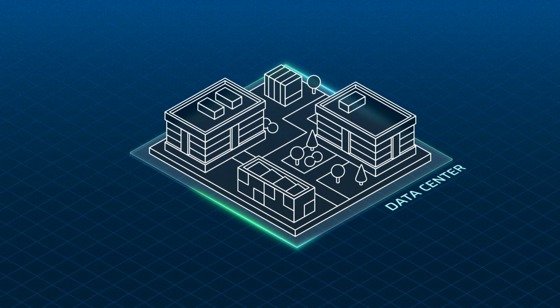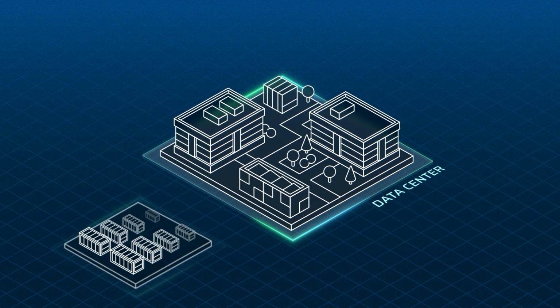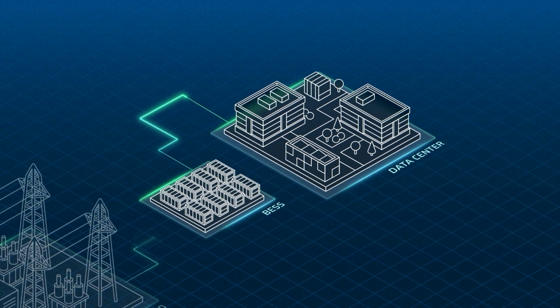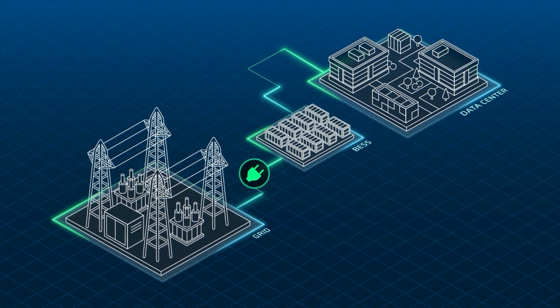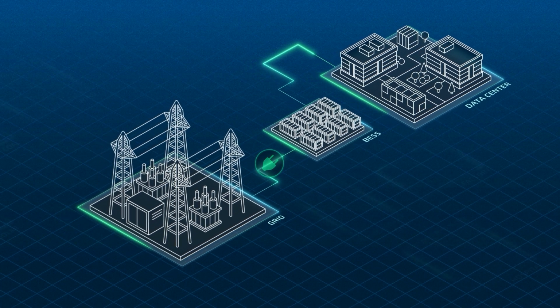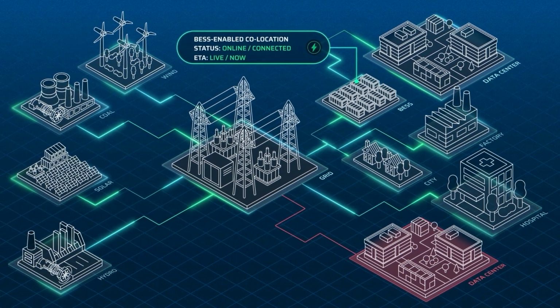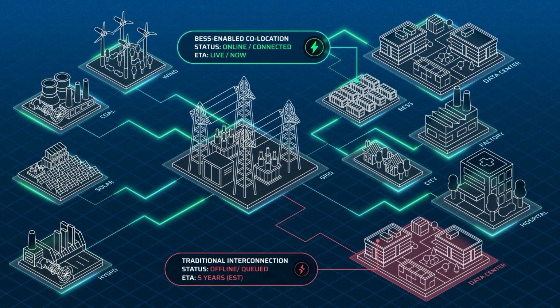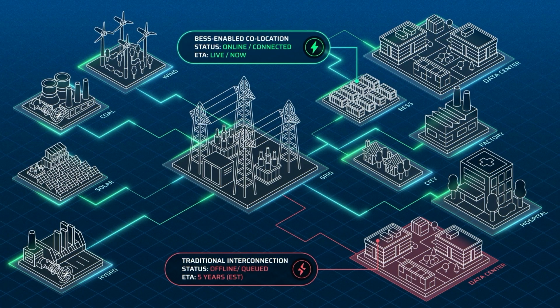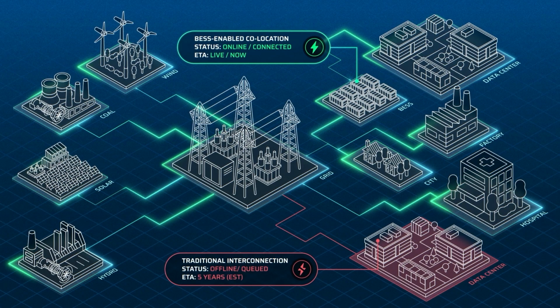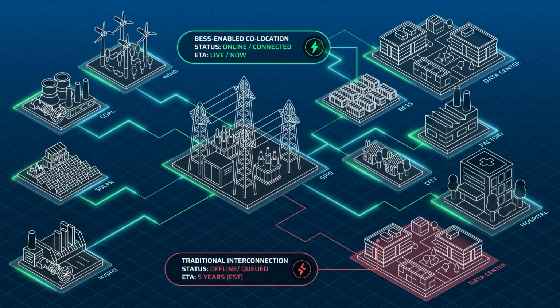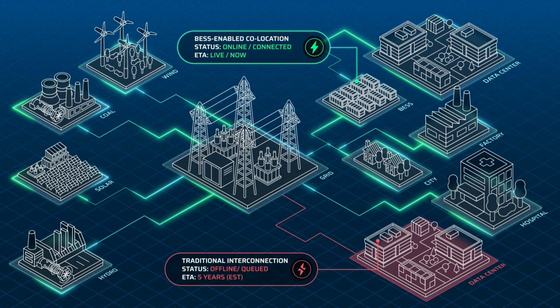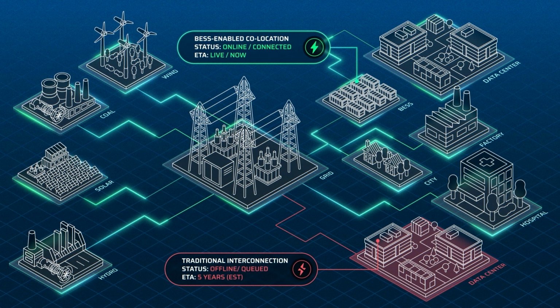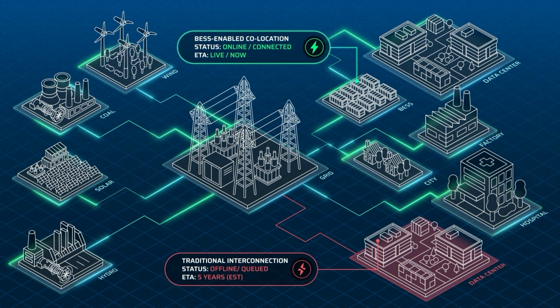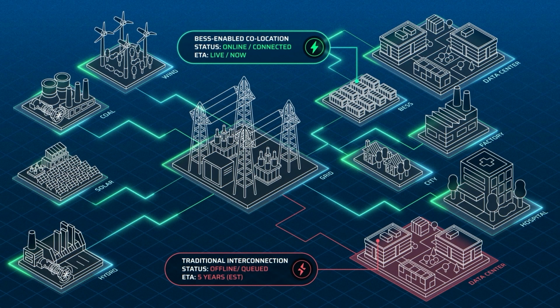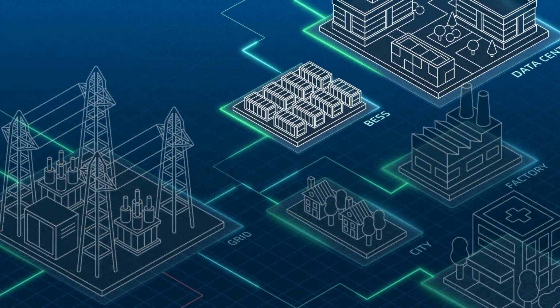At its core, co-location means pairing a generation or load asset with battery storage that has a single point of interconnection with the grid. By bringing their own power capacity on-site, developers can bypass or accelerate the years-long wait for traditional grid expansion. Instead of waiting a decade for the utility to reinforce the infrastructure, co-location allows you to leverage existing capacity today, transforming a delayed project into a connected site.